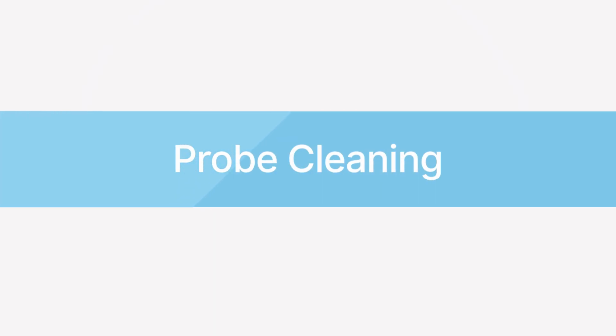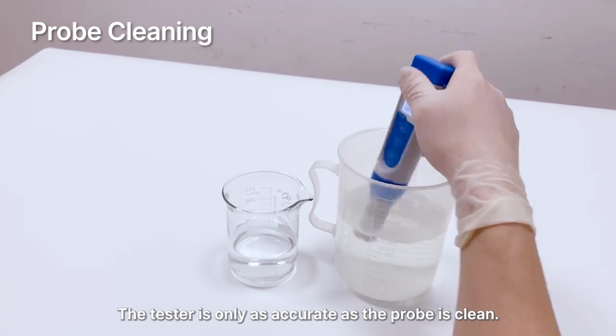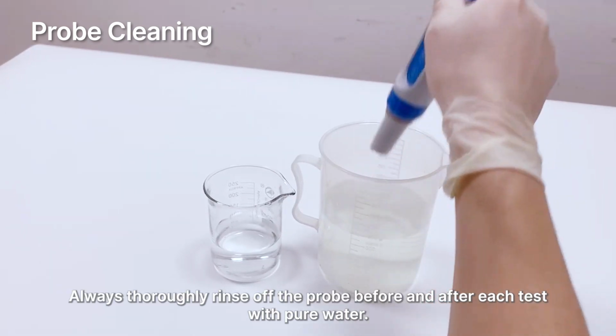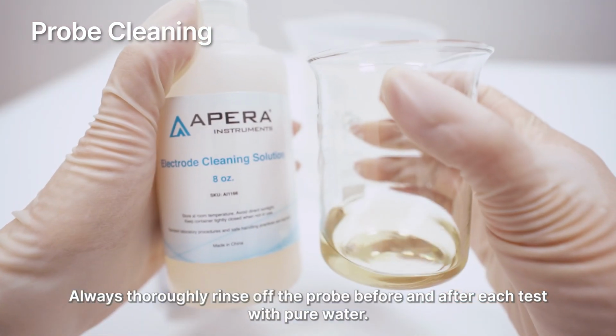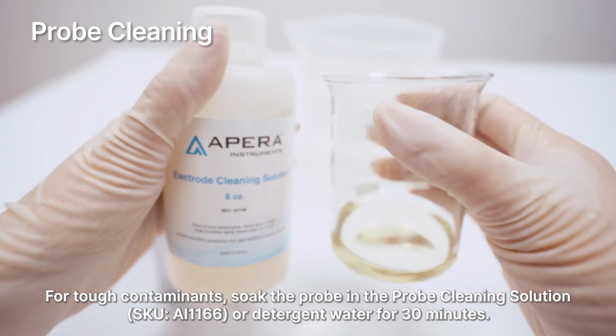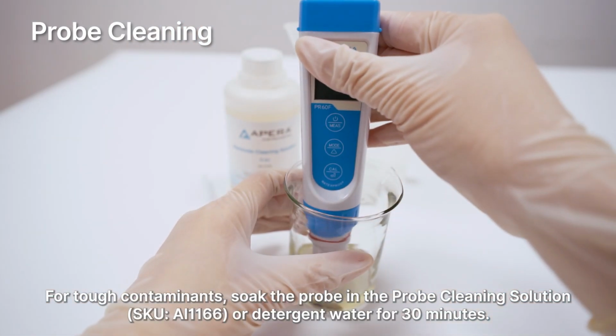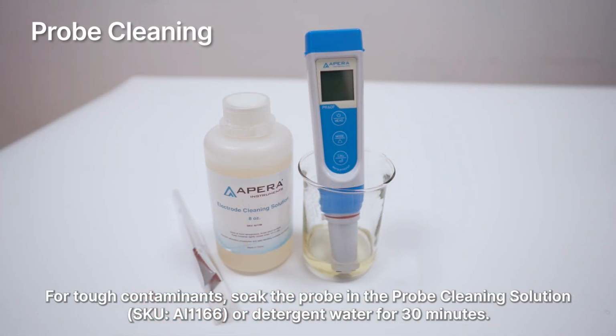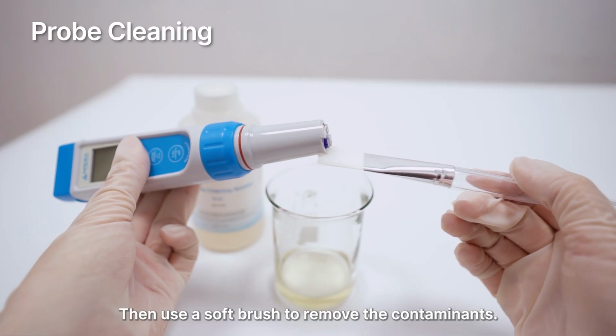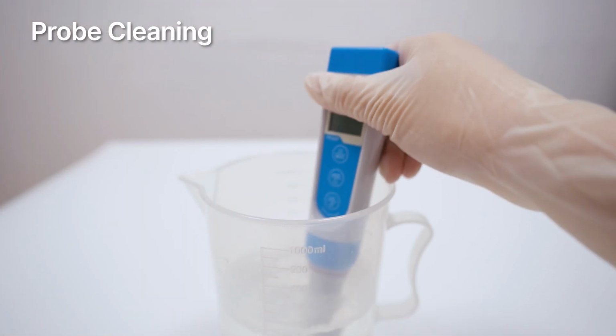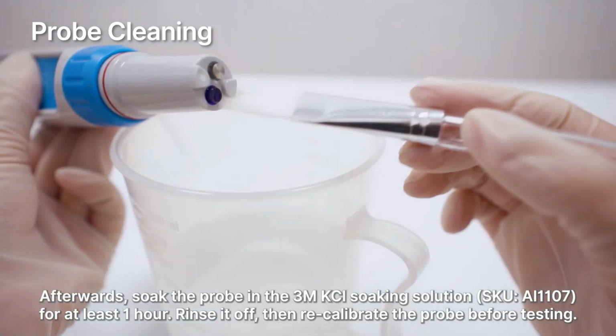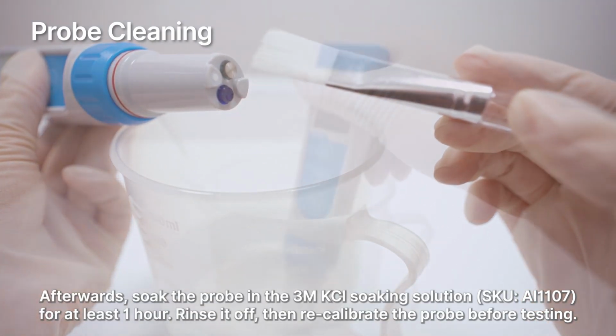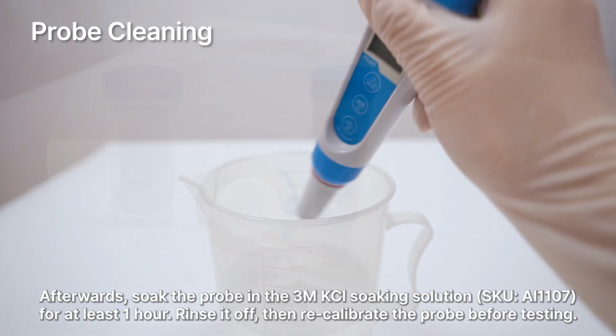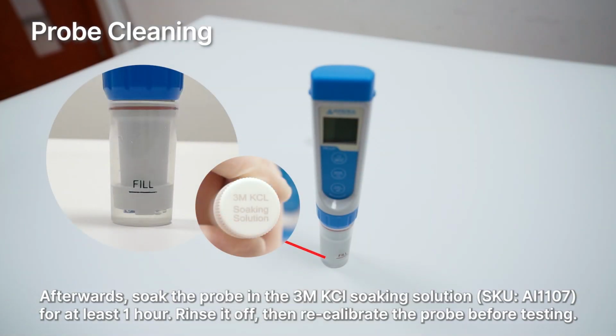Probe cleaning. The tester is only as accurate as the probe is clean. Always thoroughly rinse off the probe before and after each test with pure water. For tough contaminants, soak the probe in the probe cleaning solution or detergent water for 30 minutes. Then use a soft brush to remove the contaminants. Afterwards, soak the probe in the 3M KCl soaking solution for at least 1 hour. Rinse it off, then recalibrate the probe before testing.